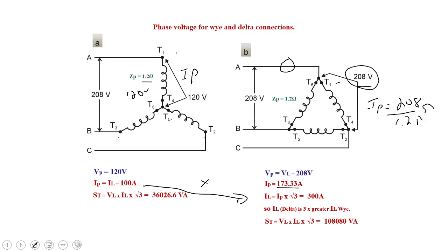The VA produced, if we were to run this through the 3-phase formula, V line times I line times √3, is 36,026.6 VA in Y. In delta, with line current being 3 times greater, we're going to get 108,080 VA. So 3 times the VA, right? And therefore, it'll be 3 times the true power, because it's the same power factor. These are the same coils, and 3 times the horsepower.